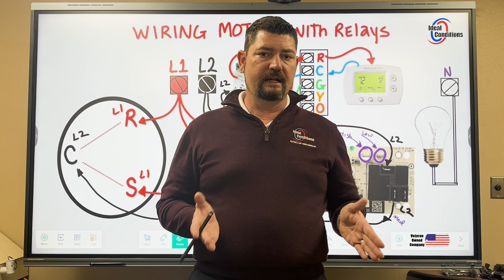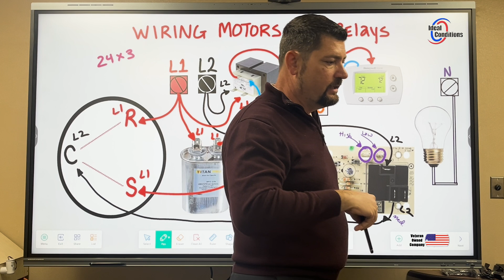If we did some quick math, let's find a color we can use. We can just do some math up here. In a 24-hour span, we would multiply that by 3 off cycles. If there was a 10-minute on, 10-minute off, 10-minute on, 10-minute off, 10-minute on, and a 10-minute off, then that's 3 cycles per hour in a 24-hour period for cooling. That means it is cycled off 3 times per hour, so we can simply say that's 72 minutes. How I get to 72 minutes is each one of these represents 1 minute. So if every hour is 3 minutes it was running, trying to shut off, then in a 24-hour span, that was 72 minutes.